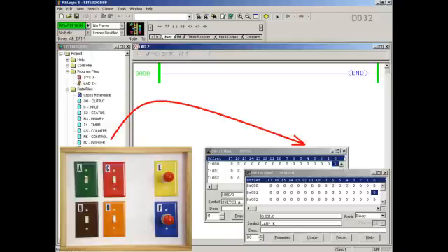Now let's see what that same operation looks like in the RSLogix software. And this could be misleading. When you flip switch A on and off, the bit changes from a 1 to a 0 so fast that it certainly does look like the transfer happens instantly. But it doesn't. That's a misconception. Actually, the transfer happens only once per scan cycle, precisely on step number 1.